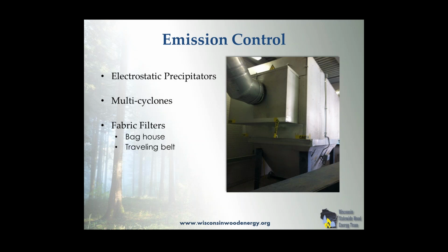Where emission controls here for an electrostatic precipitator, it's easy to reach 0.07 or 0.03 pounds PM per million BTUs of input, which are the required standards for units up to 30 million BTUs an hour, and above 30 million BTUs an hour is 0.03. Multicyclones, typically we can tune them to get in the range of less than 0.2, 0.15, or 1.5 pounds to 2 pounds per million BTUs of input is typically the range they'll operate at.